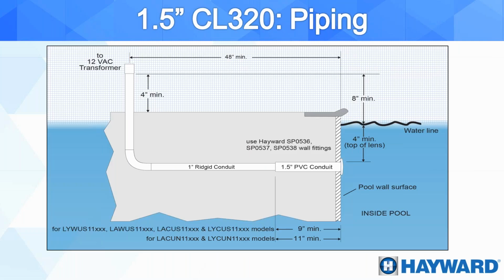And here are some recommendations on how we should be doing the electrical connections on the lights. In this case, we are showing you how to install a ColorLogic 320. Remember, the ColorLogic 320 goes inside a 1.5-inch pipe. So here we can see minimum 4 inches below the water level. We have that 1.5-inch pipe, and then that 1.5 inch is reduced to 1-inch conduit, and that inch conduit is going to go back into our junction box.